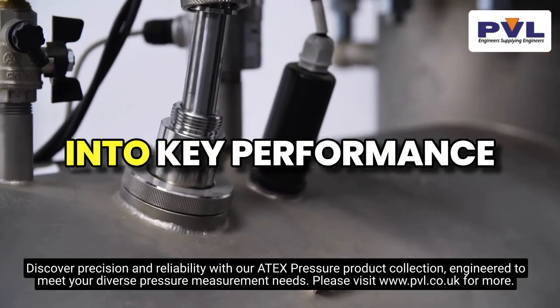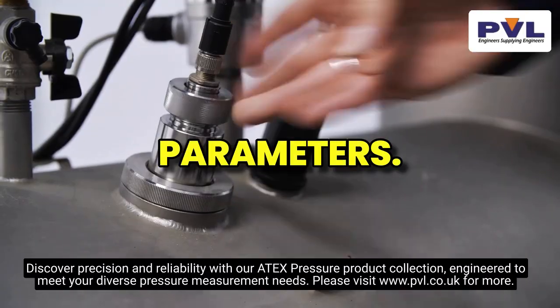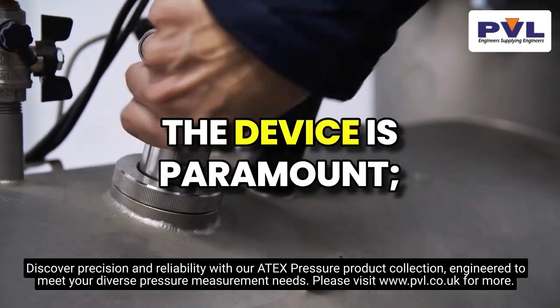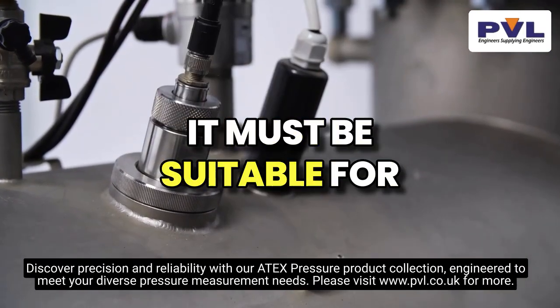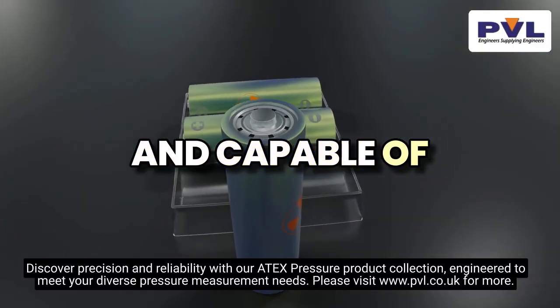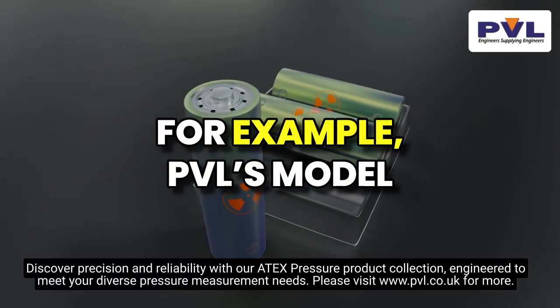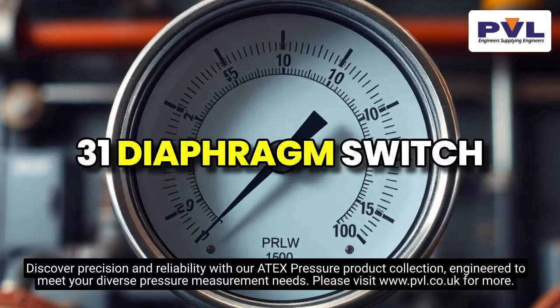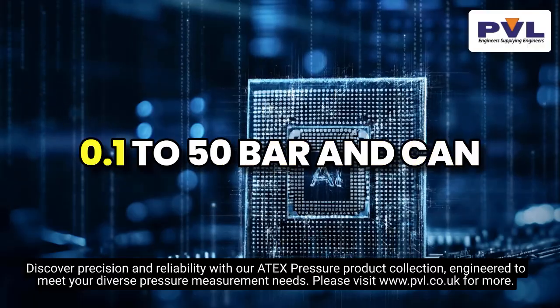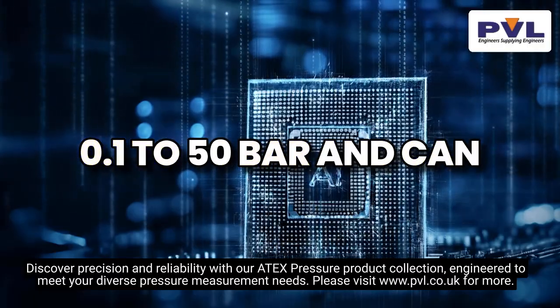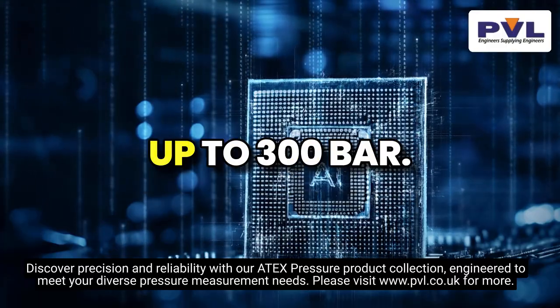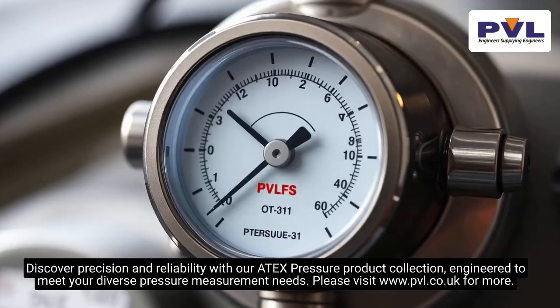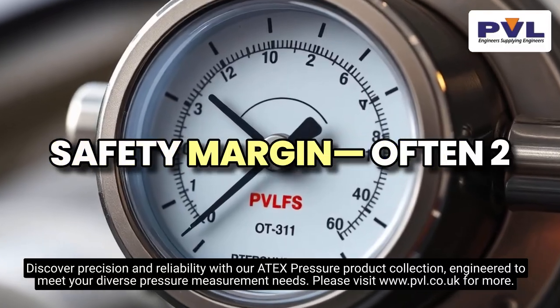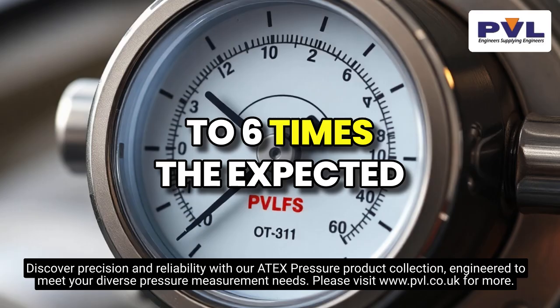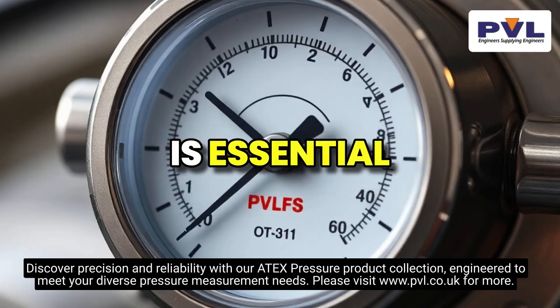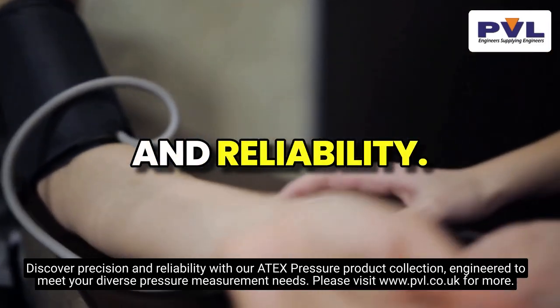Now let's dive into key performance and mechanical parameters. The pressure range of the device is paramount. It must be suitable for the specific application and capable of handling overpressures. For example, PVL's Model 31 diaphragm switch has a range from 0.1 to 50 bars and can tolerate overpressures up to 300 bars. Choosing a device with an adequate safety margin, often 2 to 6 times the expected overpressure, is essential for longevity and reliability.